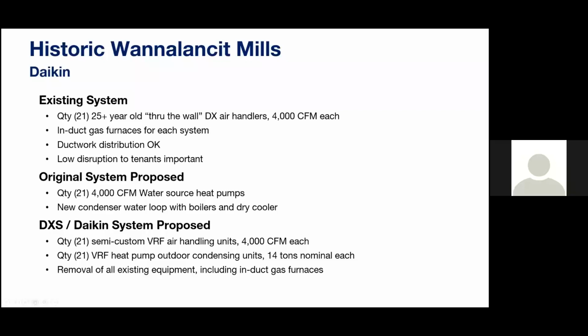So they of course were looking to replace the existing equipment, as I mentioned, and ask the question that continues to come up very often, which is how do I electrify the building, or how could they heat their building without gas? So they looked at a few different options as new systems. One of them was a full condenser water loop with dedicated water source heat pumps for each zone. With this system, you would need an electric or even gas boiler to moderate the water temperature in the winter, and then a dry cooler or a cooling tower to moderate the water temperature in the summer. So with this, you would need an entire hydronic piping network to be installed, along with the additional pumps to move that water around. So they were also looking at simple on-off water source heat pumps, which were not that efficient compared to variable speed VRF systems.